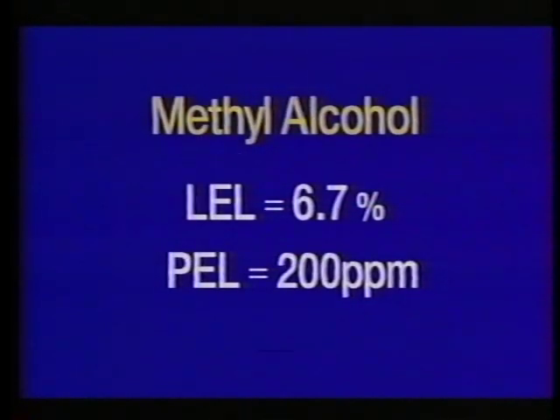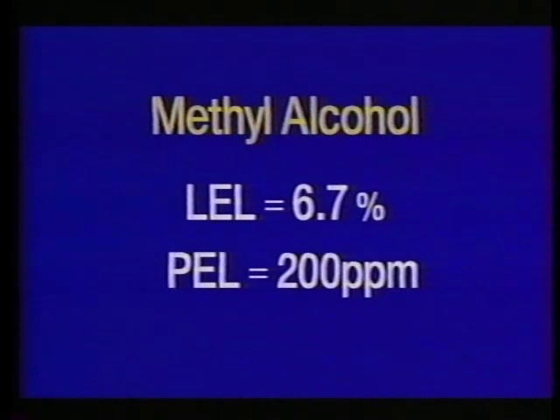The PEL is OSHA's permissible exposure limit — the highest concentration in air of a chemical substance to which employees may be exposed. The LEL, or lower explosive limit, is a much higher concentration at which a chemical gas or vapor will burn or explode if an ignition source is present. Methyl alcohol, for example, has an LEL of 6.7% in air, which is equivalent to a concentration of 67,000 parts per million — more than 300 times higher than its PEL of 200 parts per million.